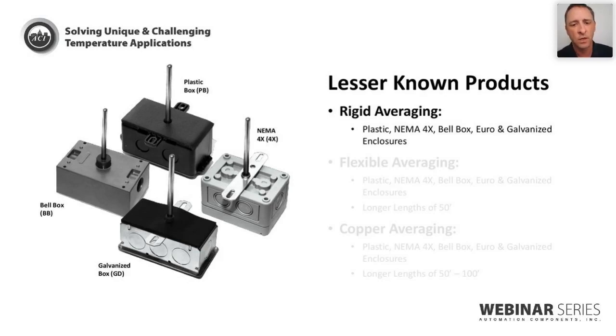Moving on to some of the lesser known configurations that can also help solve some of these unique or challenging applications. Start by talking about our rigid averaging sensors. They're going to look very similar to a standard duct sensor, but whereas a duct sensor has one sensing element mounted at the tip of the probe, a rigid averaging sensor has multiple sensors mounted throughout the length of the probe to give you an average across that space. So whether it's mounted in a duct or a mixing box, they can be mounted vertically, pointed down, to get an average across the stratification of the duct or the mixing box. And these are available in 12, 18, 24, 36, or 48-inch lengths.